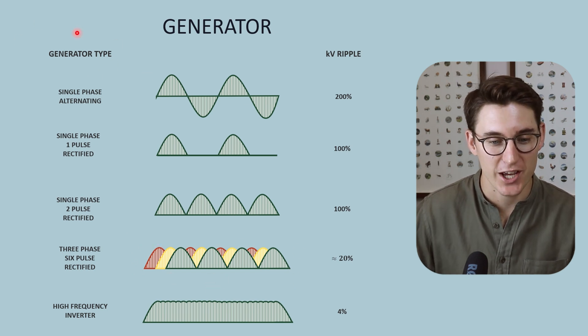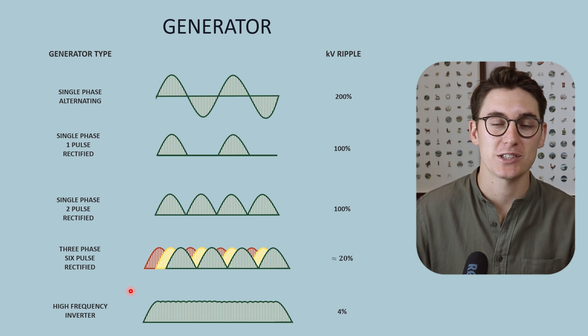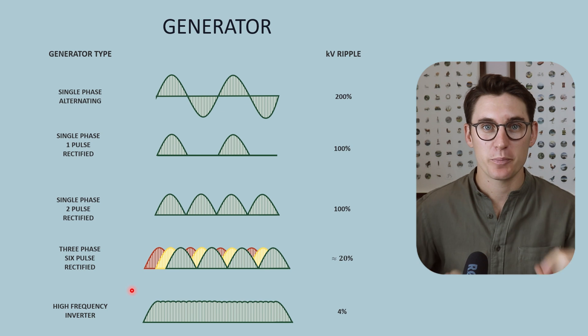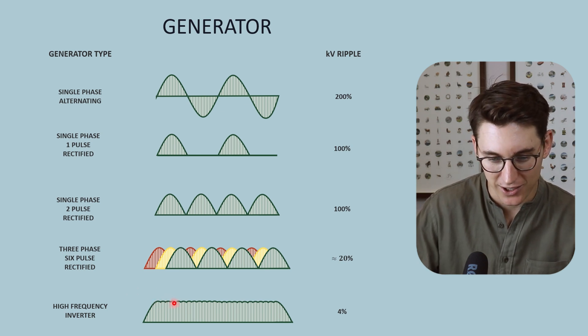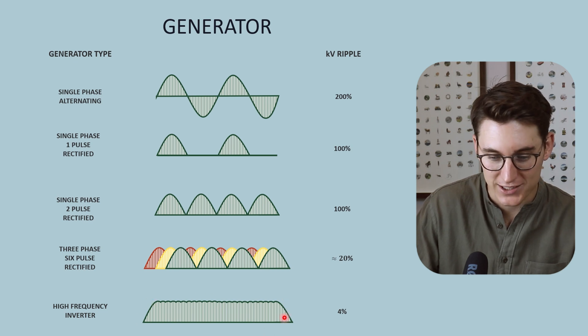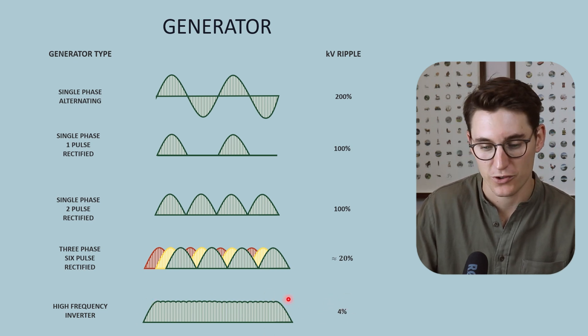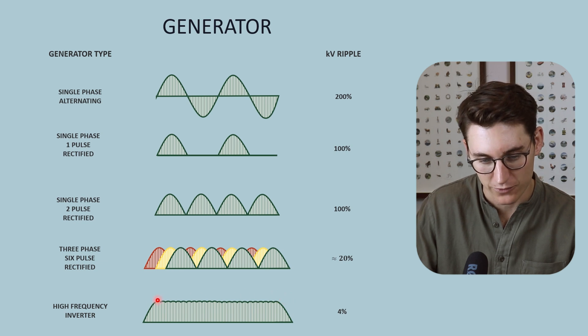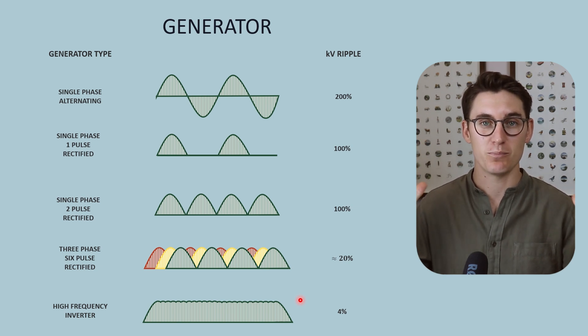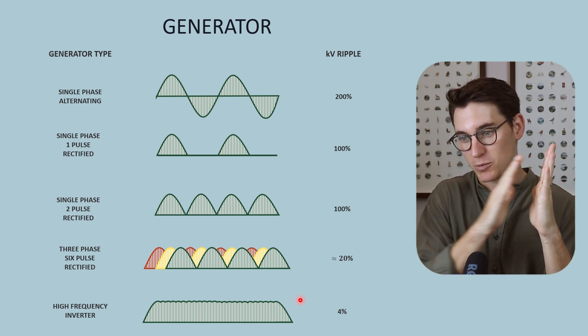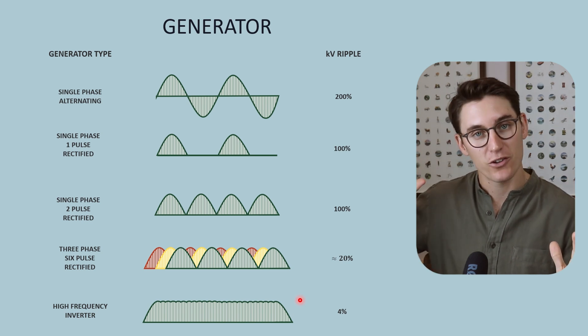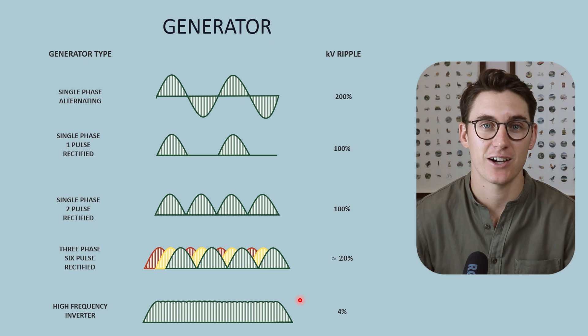We can also use a generator known as a high frequency inverter, which places multiple phases of current over one another, getting those peaks very close together. With these peaks close to one another and currents rectified, we achieve a very small voltage ripple — normally less than 4% voltage ripple. Our potential between cathode and anode is much more consistent, giving us a much more constant flow of electrons towards our anode and a much more constant stream of X-rays leaving our X-ray machine.